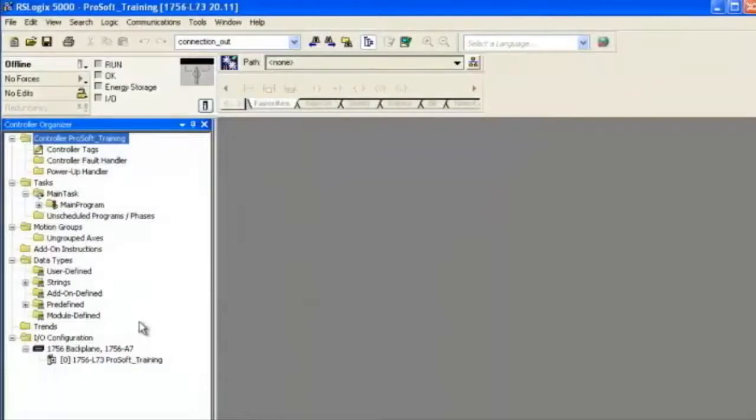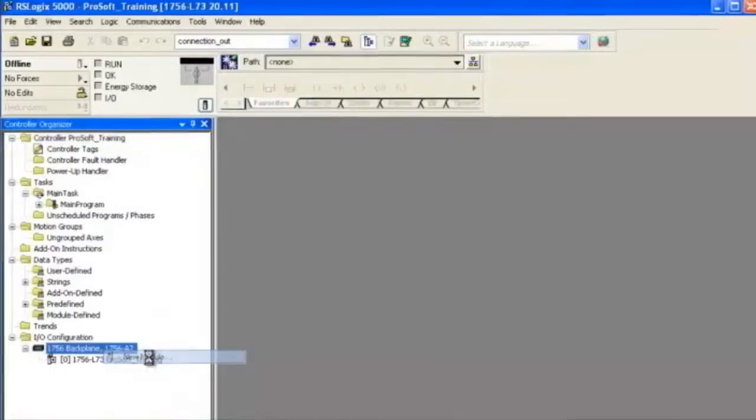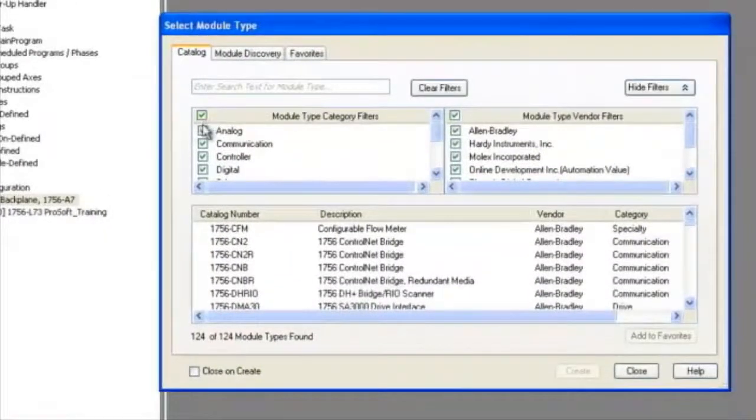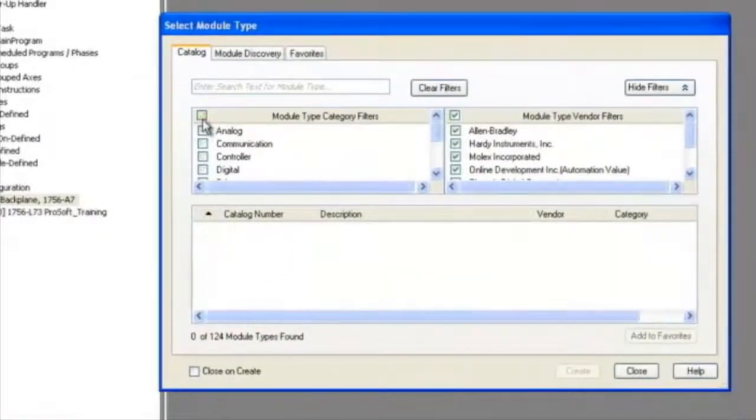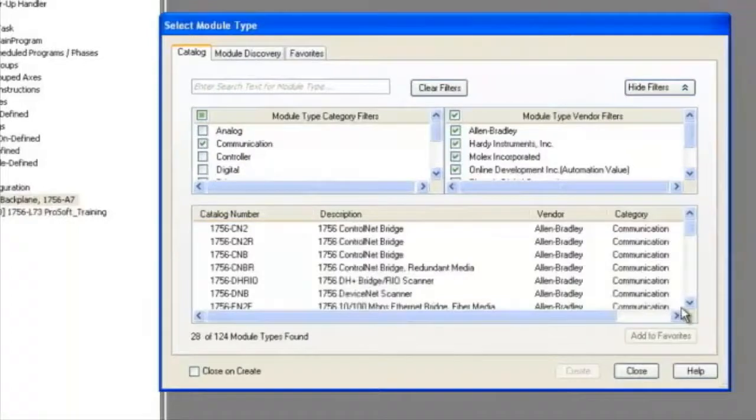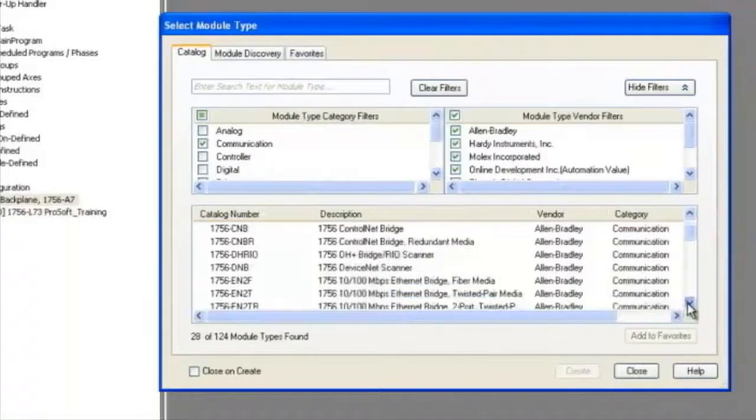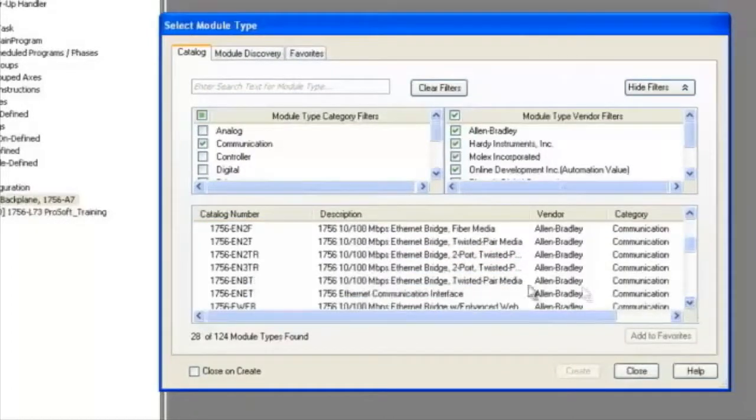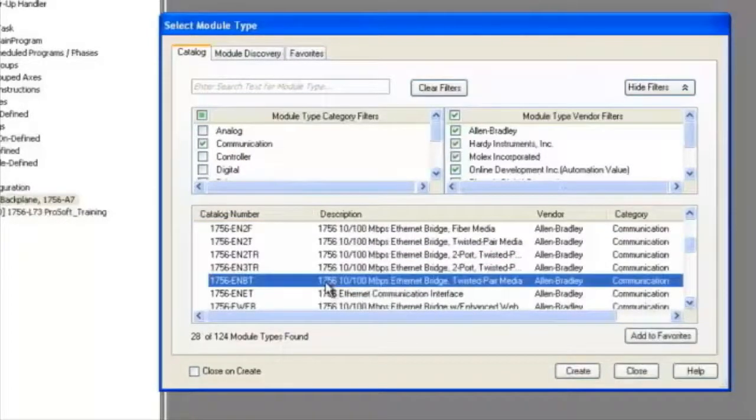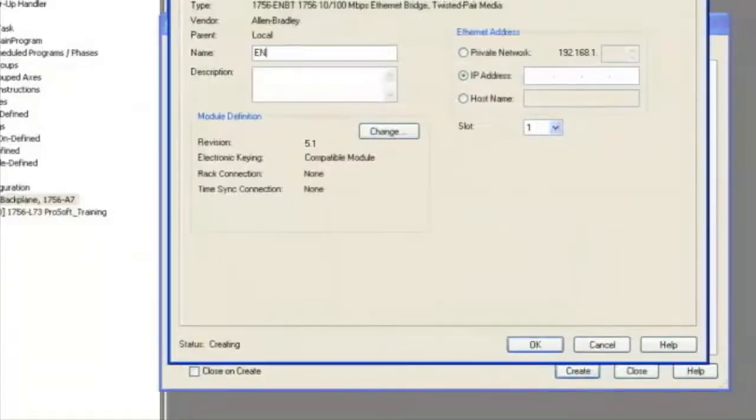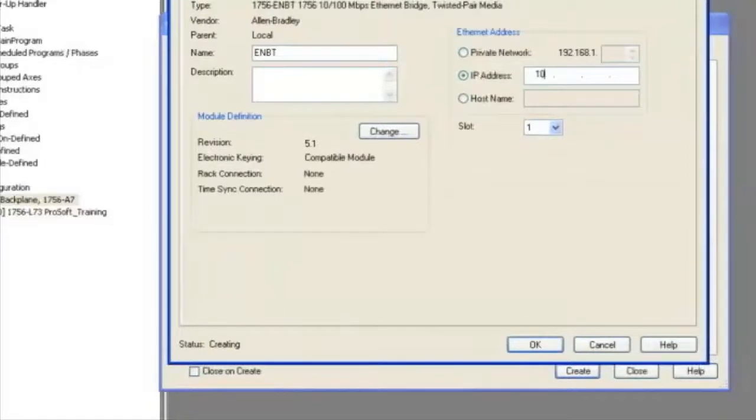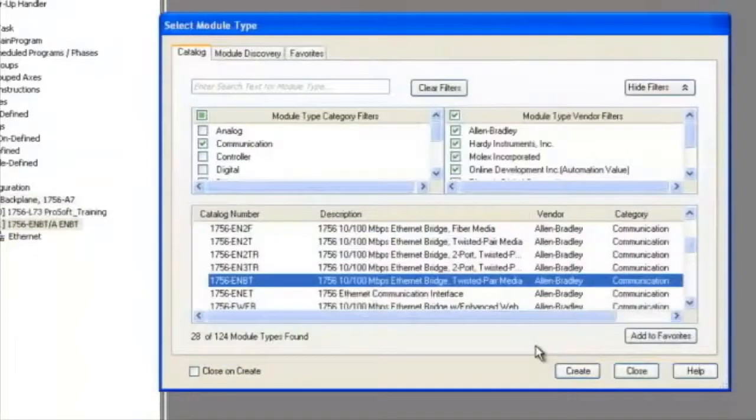Select new module. We're going to filter it by type and choose communication. We'll drill down to the 1756 ENBT. Select this module and click create. Name it ENBT and give it the IP address of 10.1.2.110. We'll leave that in slot one. Select OK and close this dialog box.